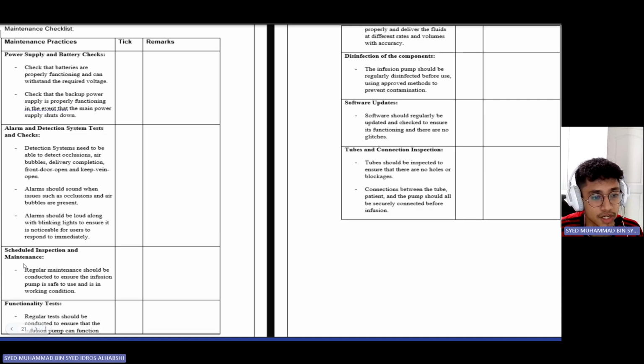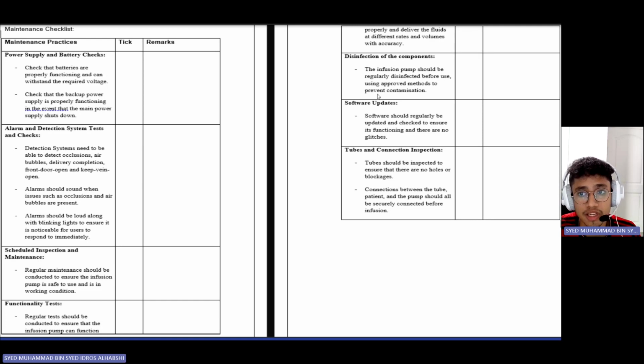Thirdly, scheduled inspection and maintenance. Regular maintenance should be conducted to ensure the infusion pump is safe to use and is in working condition. Fourth, we have the functionality test. Regular tests should be conducted to ensure that the infusion pump can function properly and deliver the fluids at different rates and volumes with accuracy. Next, we have disinfection of the components. The infusion pump should be regularly disinfected before use, using approved methods to prevent contamination.